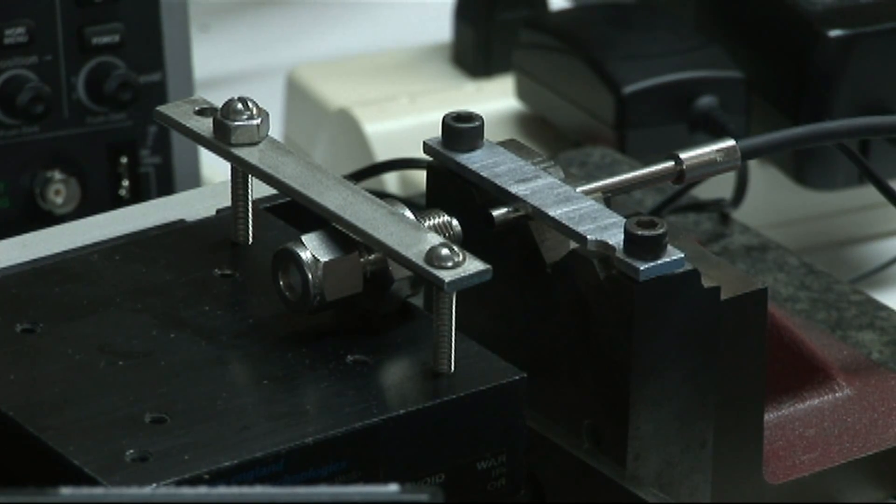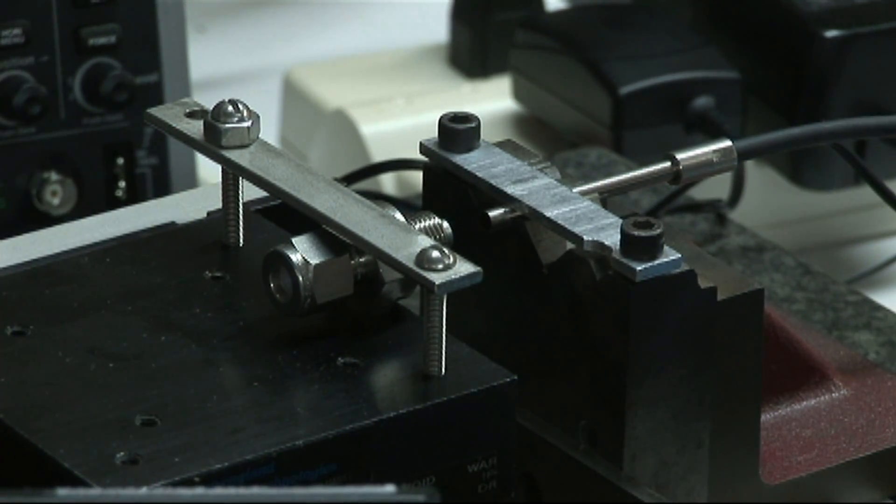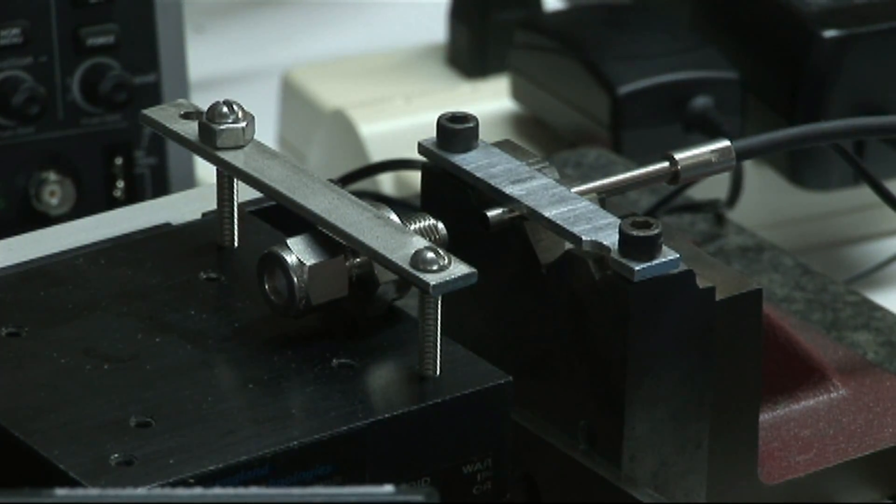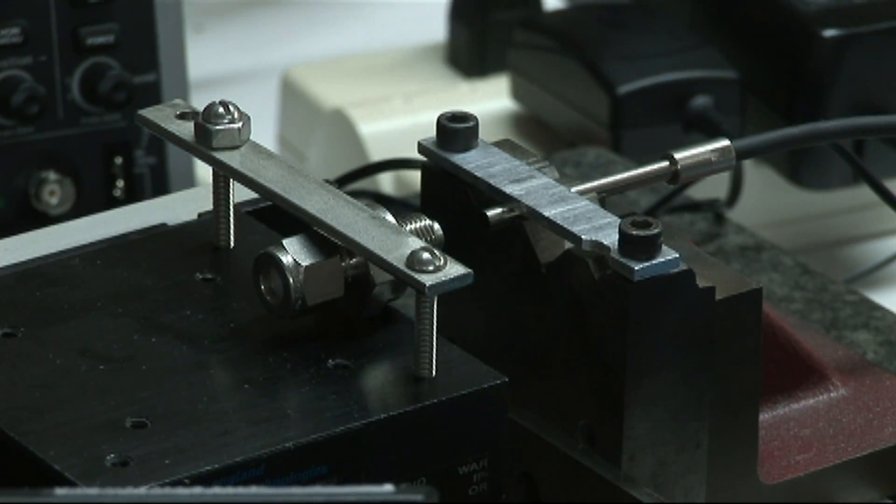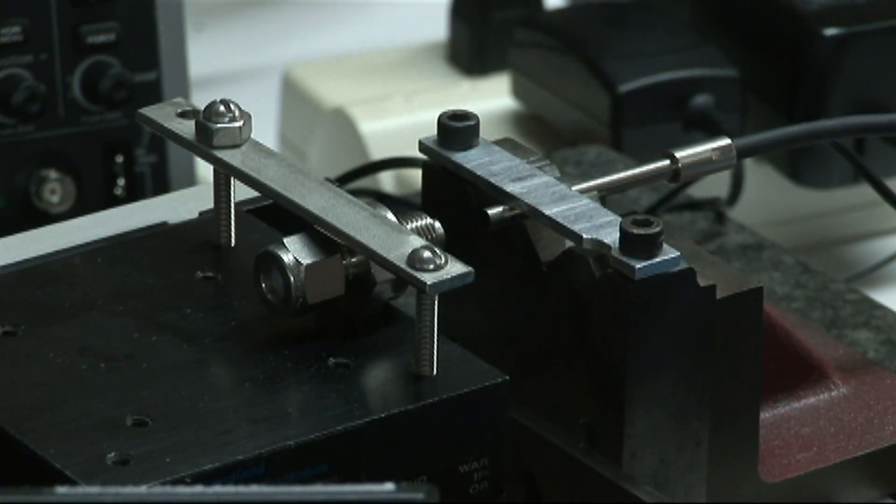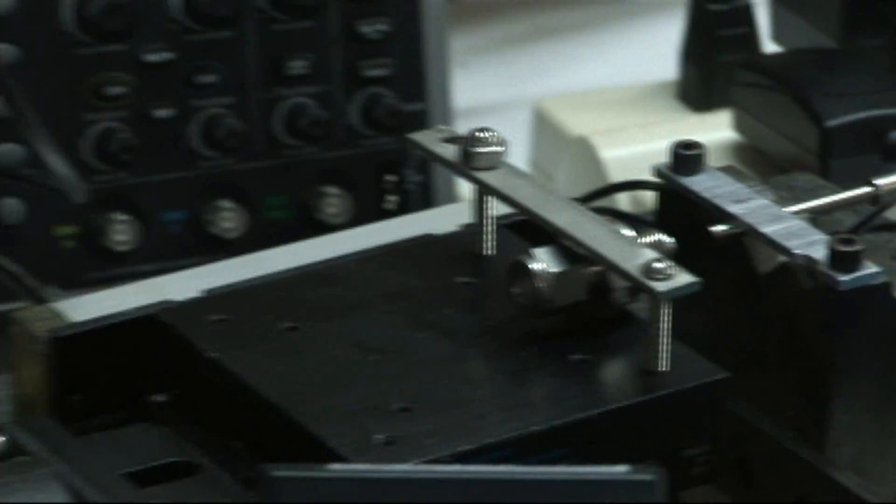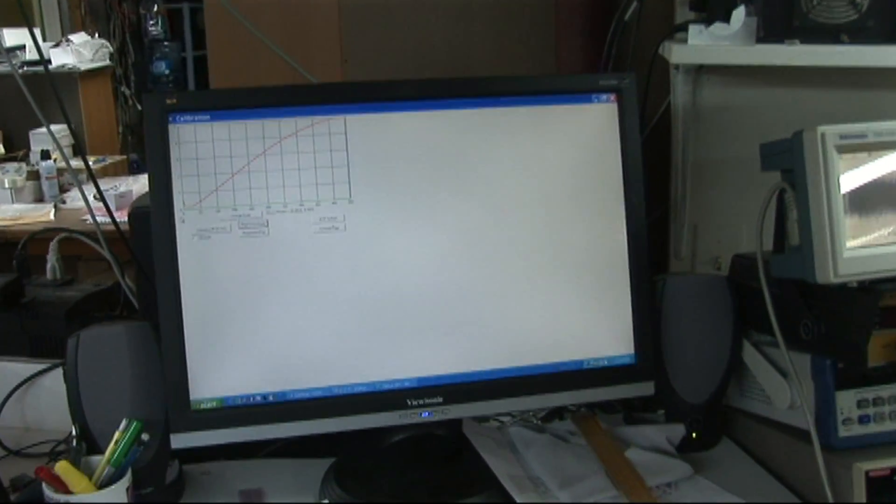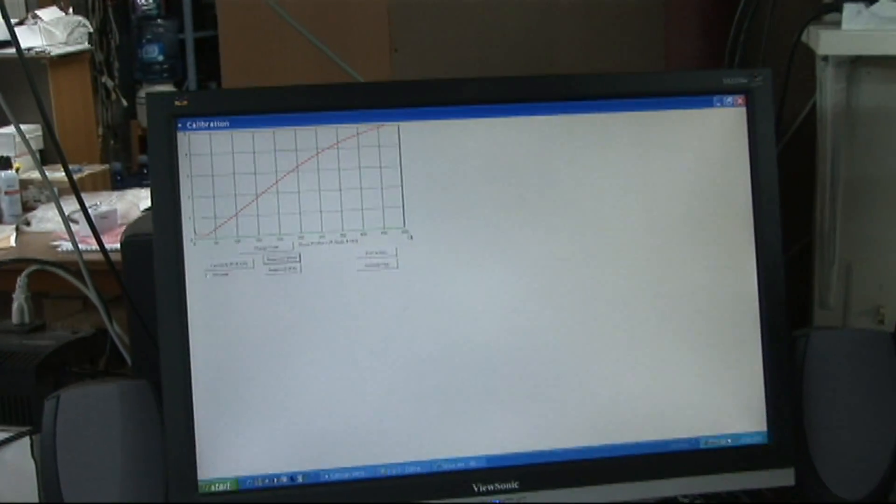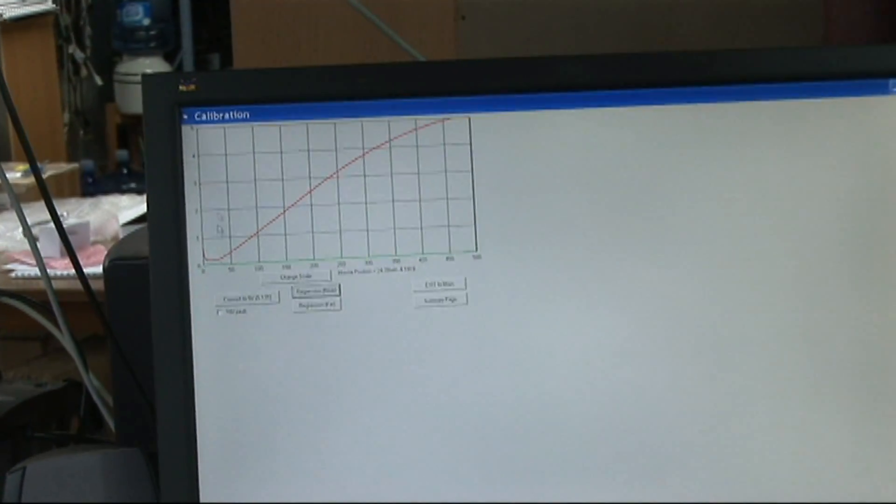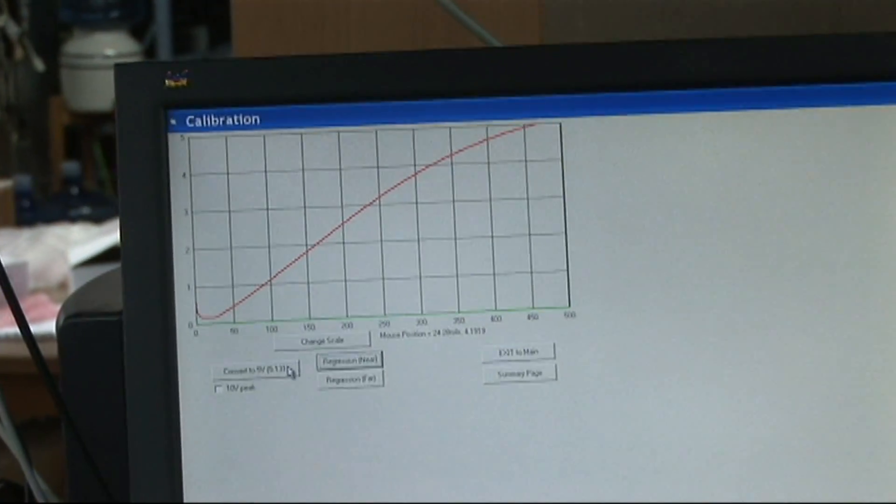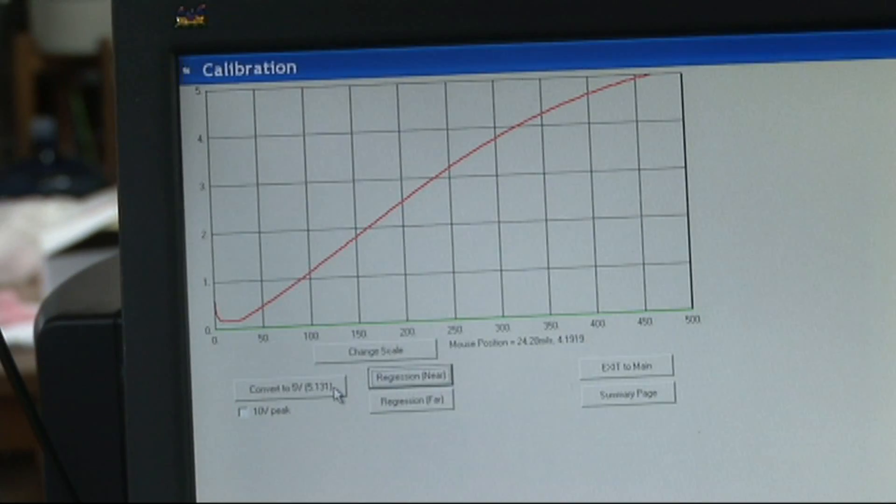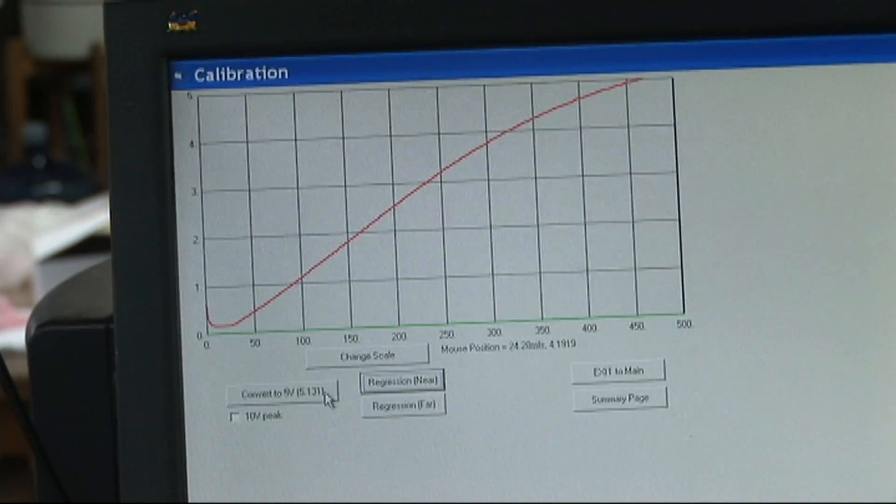Now, when this is done, we'll be at exactly one-half inch gap from the sensor. And now, if we could pan over here to the screen, you can see the result of this calibration. We have from zero to five hundred mils, zero to five volts up here. You can see that the sensor is maximized at 5.131 volts.